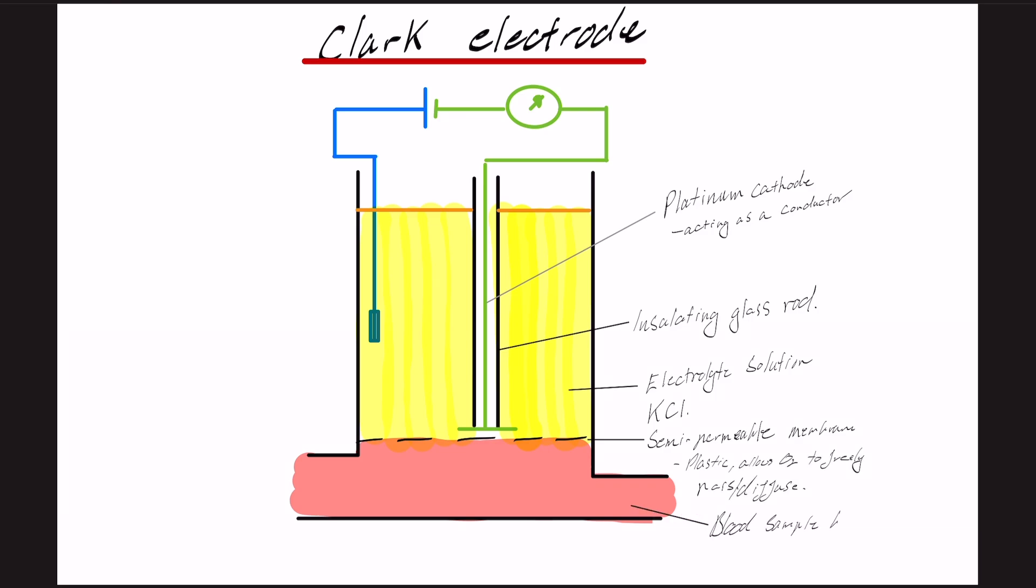So as I mentioned in green, this is our platinum cathode, and it's acting as a conductor. It's insulated by a glass rod, and it's surrounded by this electrolyte solution, which is usually potassium chloride. And there's a semi-permeable membrane. It's usually plastic or teflon, and only allows oxygen to freely pass through it or diffuse. And then our blood sample that's being measured in red here.